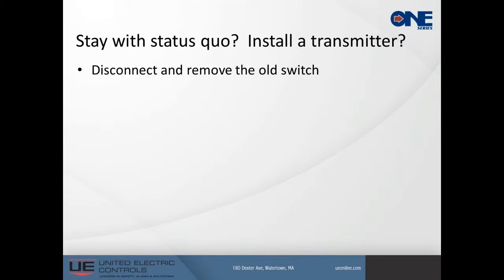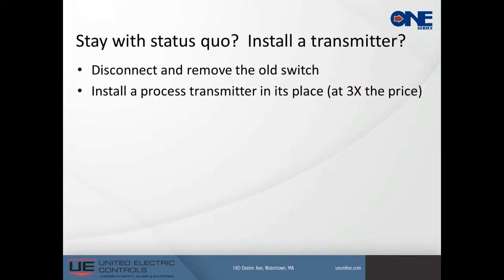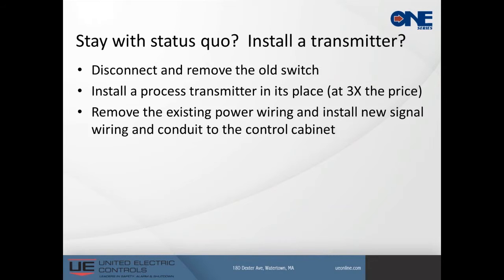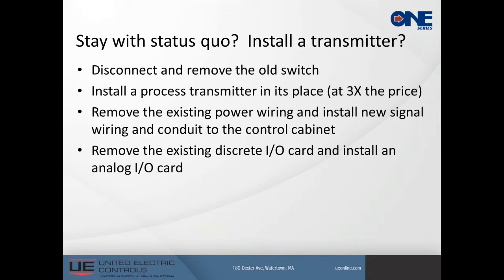Status quo in the past has been just basically disconnect and remove the old switch and go ahead and install the process transmitter in its place, drill new holes. It's about 3 times the price. And we have to remove the existing power wire. We can't install a transmitter with power wiring, so we have to install new signal wiring and conduit and such back to the control cabinet. And then the next piece of the puzzle is we've got to remove the existing discrete I/O and spend quite a bit of money and install analog.